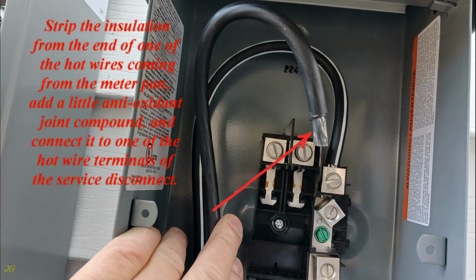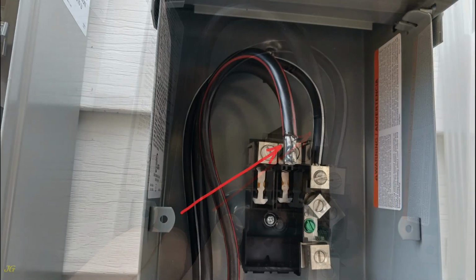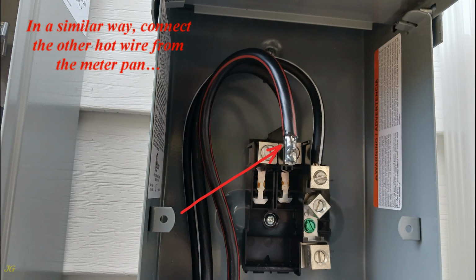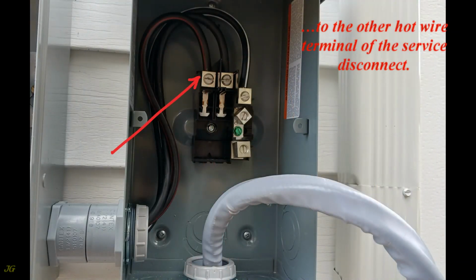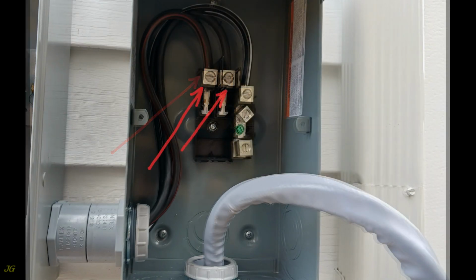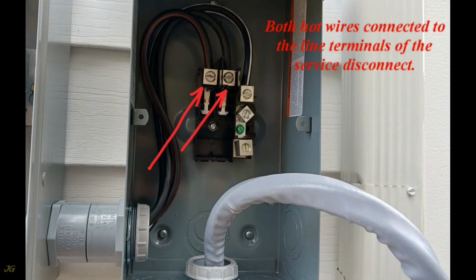Strip the insulation from the end of one of the hot wires coming from the meter pan. Add a little antioxidant joint compound, and connect it to one of the hot wire terminals of the service disconnect. In a similar way, connect the other hot wire from the meter pan to the other hot wire terminal of the service disconnect. Both hot wires connected to the line terminals of the service disconnect.